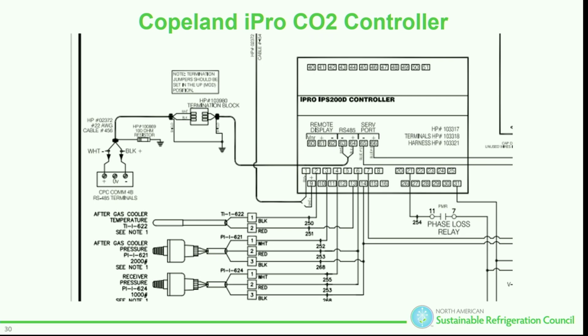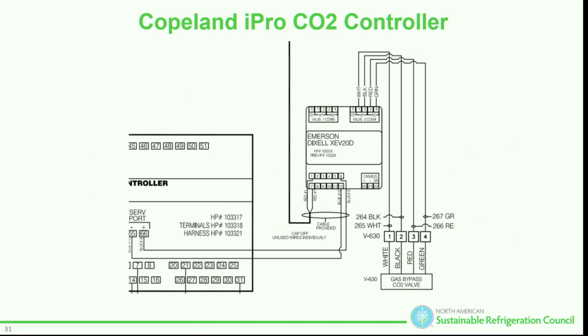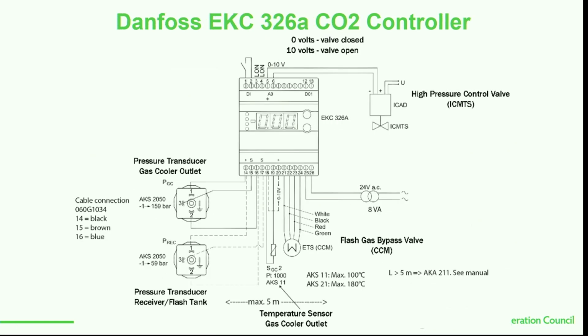Phase loss. Watch your phase loss. Each one of these case controllers, I don't care the manufacturer, they have a normally open set of contacts. You see it right here? If I open, it's going to close as soon as I get power. The controller's going to run. If I open that circuit, I'm going to go off. I'm going to shut the high pressure control out and flash gas bypass off. Right? So remember, phase loss. And a lot of the manufacturers now are going to simply put an ice cube relay there.